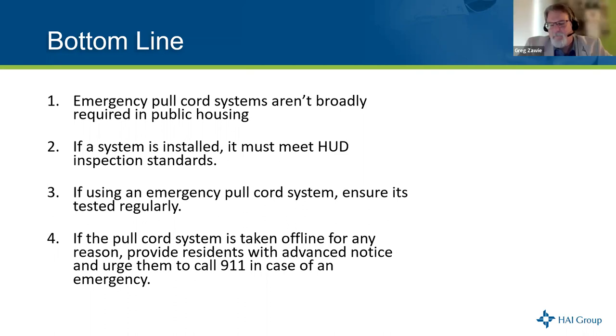Carissa's organization ran into an issue during an Inspire inspection and was told they were not in regulation, but weren't told exactly what the issue was — maybe it was the height requirement, maybe something else. Brian notes it also depends on the inspector. There is some interpretation involved, unless things are specifically spelled out. The Inspire standard for pull cords is the same as REAC — six inches off the floor. We just went through 15 Inspire inspections and it's six inches off the floor.